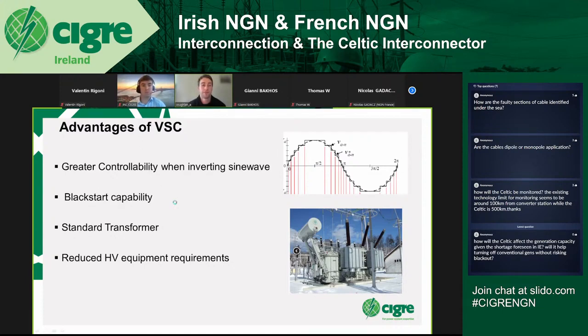Another point: this sine wave is smoother, whereas in LCC it's a lot more jagged, so there are more harmonics associated with it. These harmonics can damage transformers, so you need a transformer able to take these harmonics. With VSCs you don't need that so much, so you can use a more standard transformer, like those used in normal AC transmission systems, which is more reliable, has more spares, and is usually cheaper.